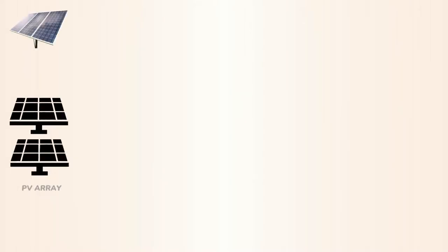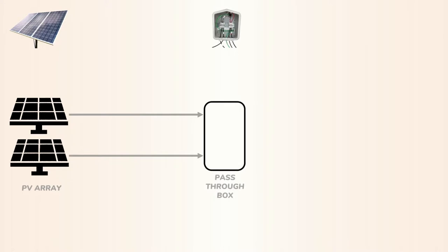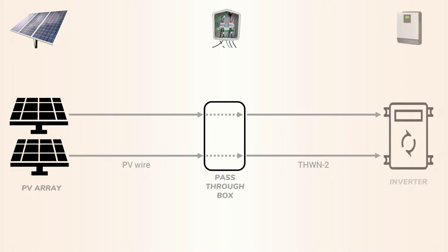Smaller PV systems having one or two strings of solar modules often use junction boxes simply to pass through each set of conductors coming from the solar array. Used in this sense, a pass-through box just provides a safe location for any electrical connections to be made. This can help whenever you're transitioning from solar PV wire to a more affordable wire that could be run downstream to the inverter or a charge controller. While fuses are not required to connect conductors inside of a pass-through box, you would need some kind of connector or a wire nut or terminal block to make the connection.